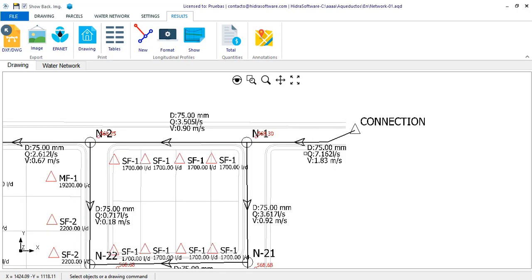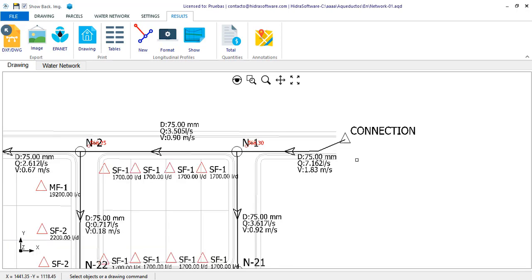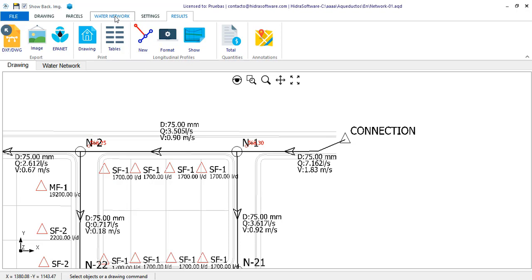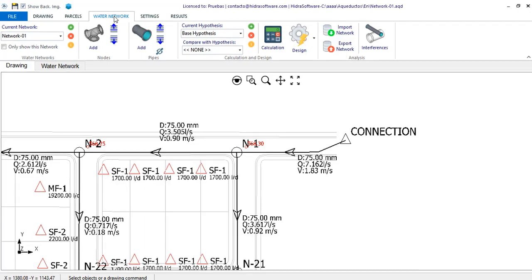When it comes to the design of water distribution networks, it is necessary that the network be loaded with the maximum daily and hourly demands in order to guarantee its operation in the most critical situation. Thus, since what has been specified or calculated automatically for nodes are average water demands, it is necessary to have a way to apply an increasing factor that allows us, easily, to obtain the demand condition required for design or calculation of the network. In aqueducts, to handle such situations, the use of calculation hypotheses has been proposed, which allows you to maintain in each project scenarios of demands or operating conditions, as we will explain in another video. In such a way you can evaluate various conditions and make a decision regarding the dimensioning of the network's components.